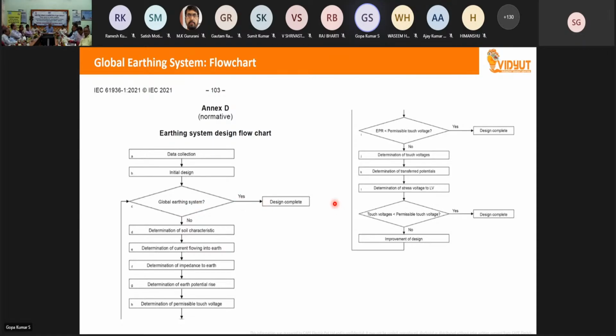It means you interconnect all metal parts of your EHV, HV, ELV, LV, everything except the current carrying conductors, into a common system, and that is called a global earthing system. By the proximity of its distance, shock voltage becomes very low, nearly zero. For example, in one of the GIS where I designed the global earthing system, when I tested, the touch voltage was about 12 volts during a 50 kiloampere fault current. This is the best system.